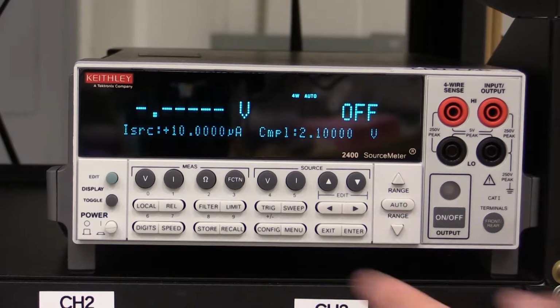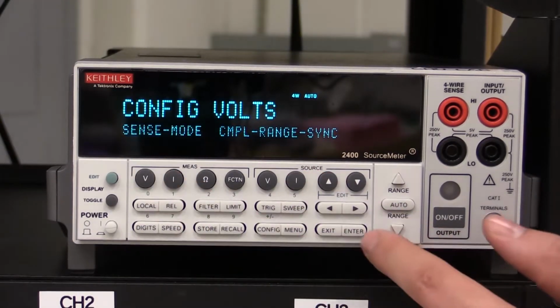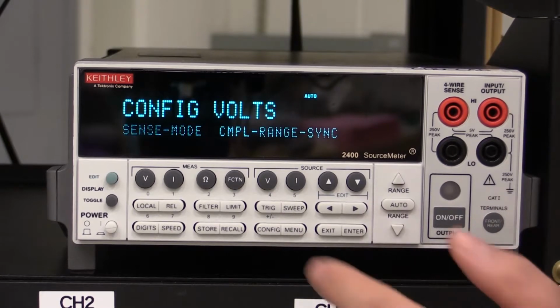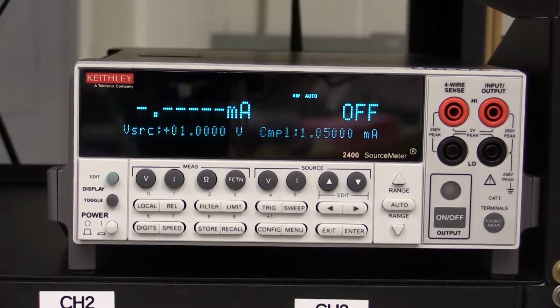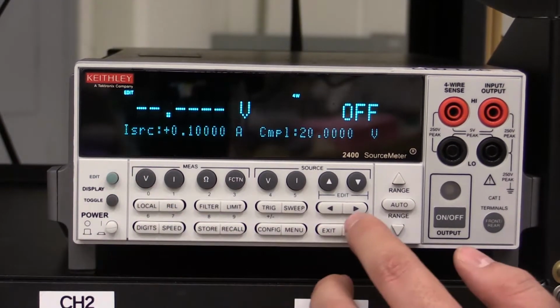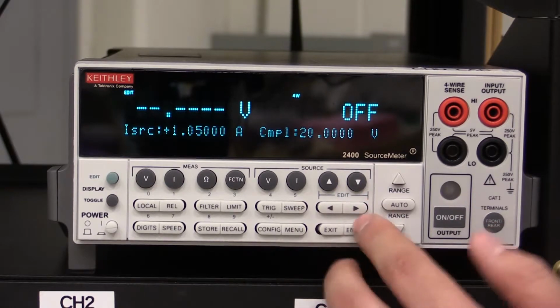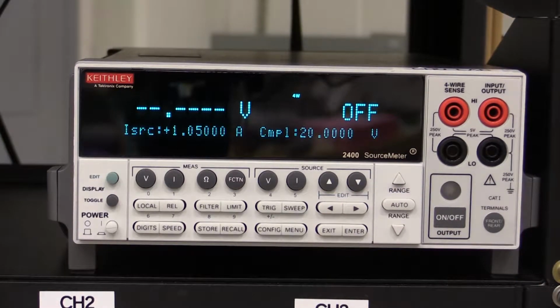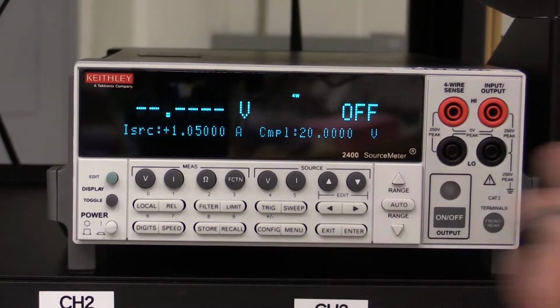We can take it out of four wire mode by going config V, sense mode, and going over to two wire. One thing to keep in mind when using this instrument is the source range and the compliance level of the instrument. So for example, if we are sourcing current and measuring voltage, and we tell it to source something on the order of 1 amp of current, you can imagine if we attach a mega ohm resistor across these leads right here, it would need a huge voltage to source that current, and there might be a safety problem there. So what the compliance voltage is, it's our safety net.